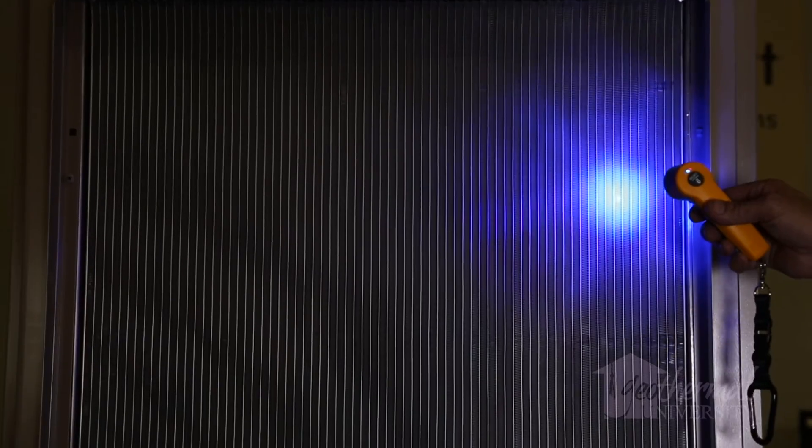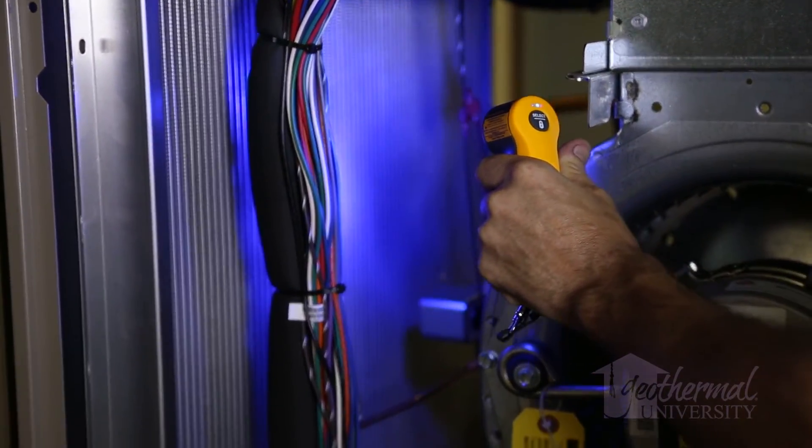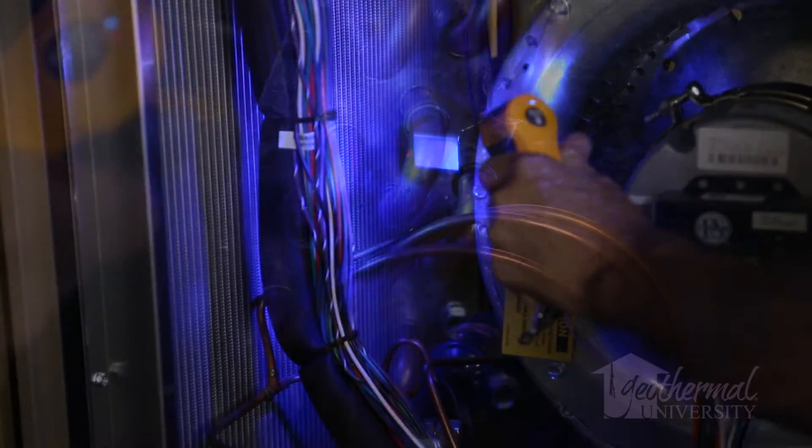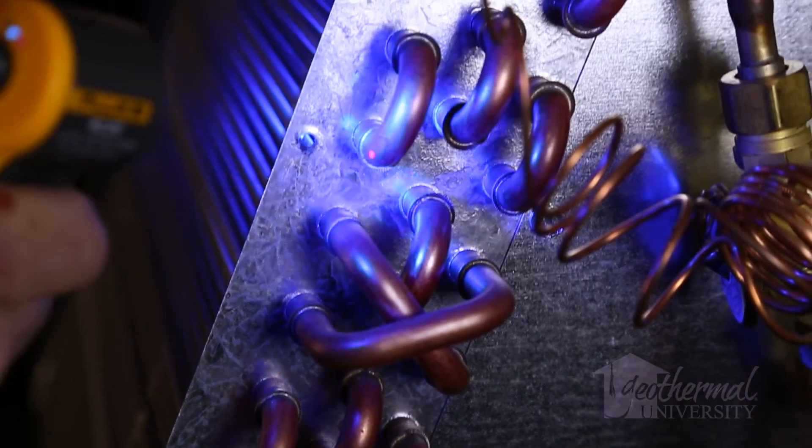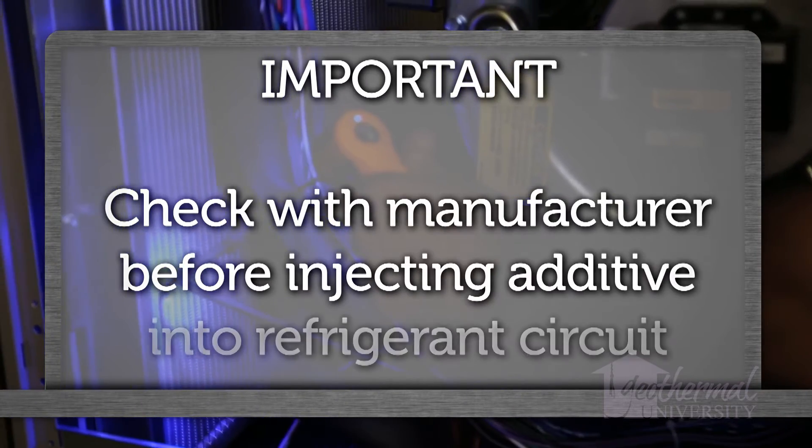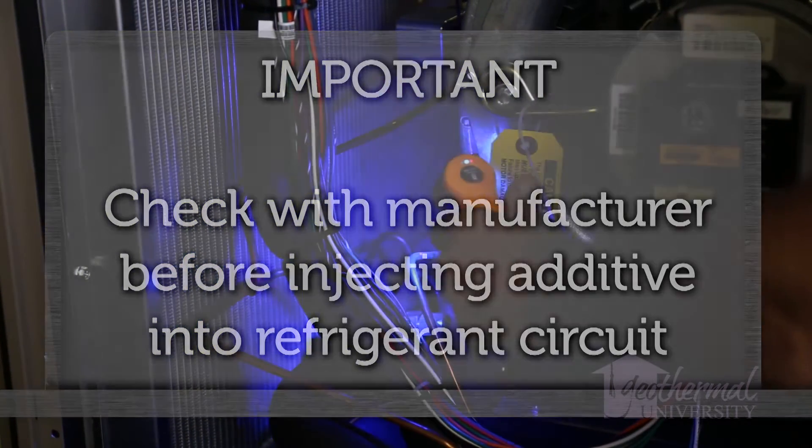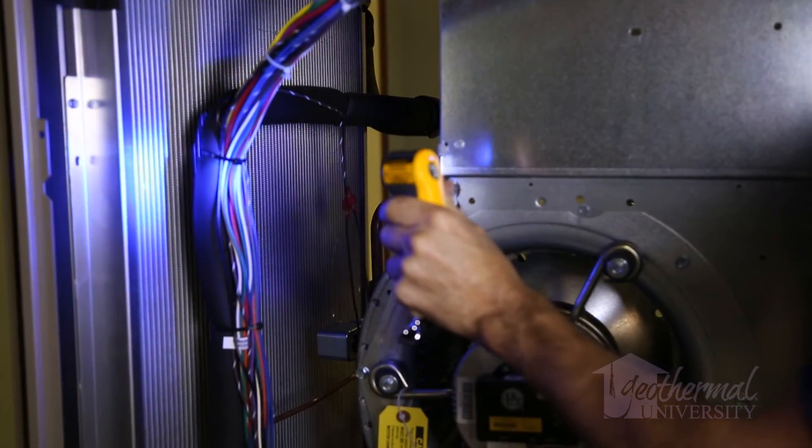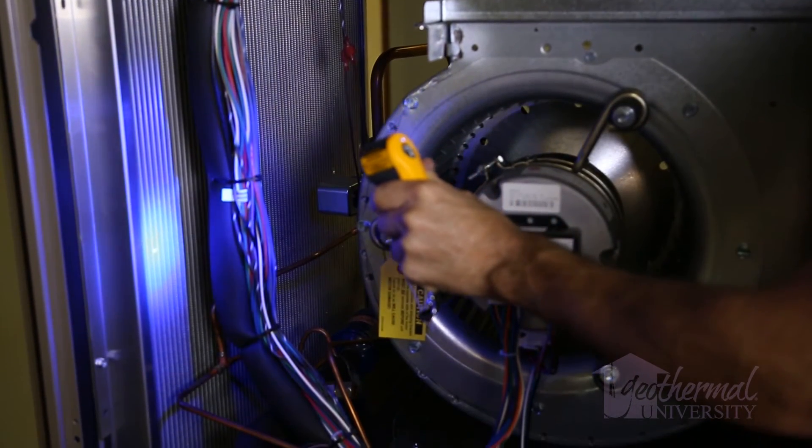This method requires adding fluorescent dye to the air conditioning or refrigeration system. The dye then mixes with the lubricant and circulates with the refrigerant throughout the system. Wherever refrigerant leaks out, so does the dye. When the system is scanned with an ultraviolet or blue light lamp, the dye glows a bright yellow green color pinpointing the location of the leak. Consult with the equipment manufacturer and or compressor manufacturer before injecting any additive into the refrigerant circuit. Many manufacturers do not approve of dye additives. Make sure the specific dye is approved by the equipment manufacturer.